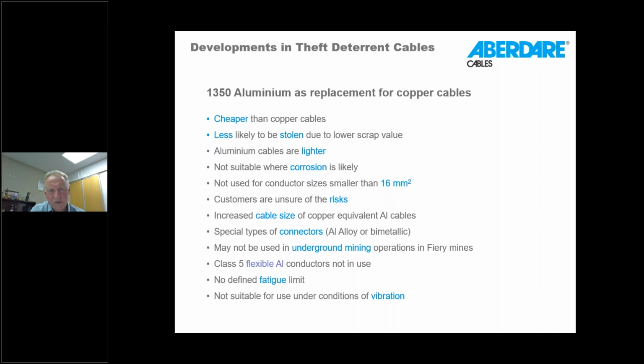You need special types of connectors, mostly bimetallic connectors to connect to, let's say, a copper busbar or different metal type, or aluminium alloy, and often mechanical type connectors are used for this type of application, which also have anti-corrosive paste inside these connectors. So the solution is there to apply aluminium. We know that in the mining environment, aluminium cables are not allowed to be used, particularly in fiery mines, due to the risk of a flash and explosion.